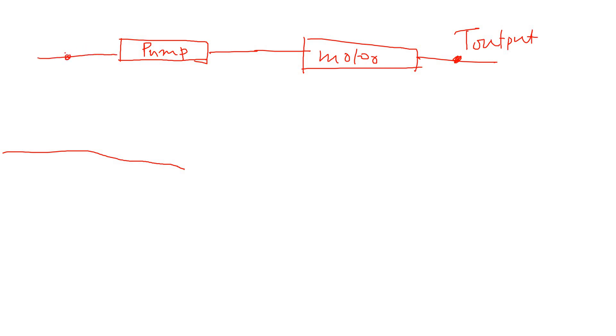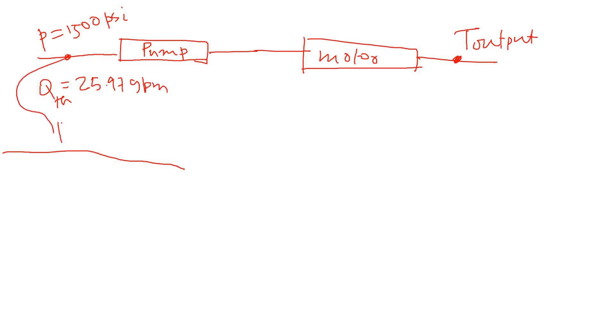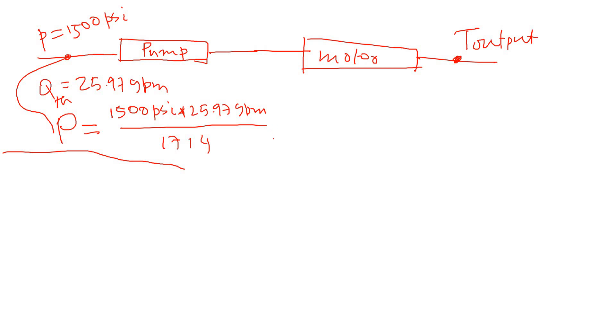We know the pressure at the pump outlet is 1500 psi, and the theoretical pump flow was calculated as 25.97 gpm. At this point, the hydraulic power P = P × Q / 1714. So P = 1500 psi × 25.97 gpm / 1714. This conversion factor gives power in horsepower, and I calculated 22.73 horsepower.